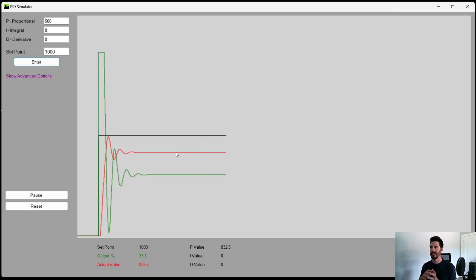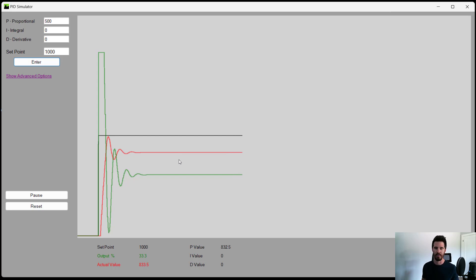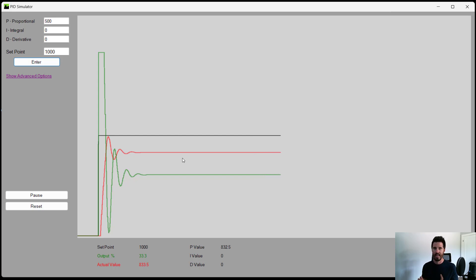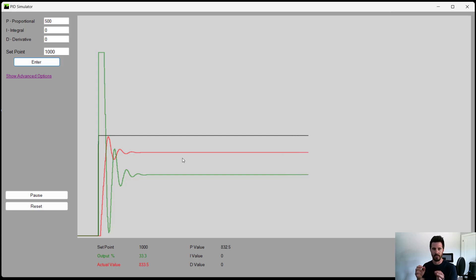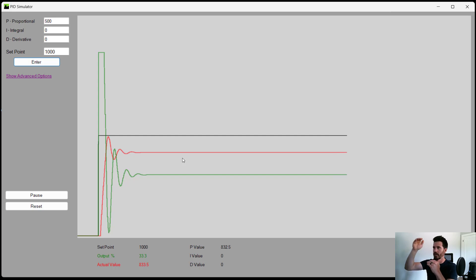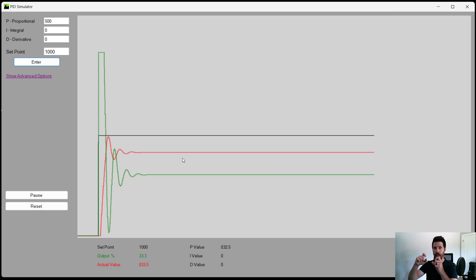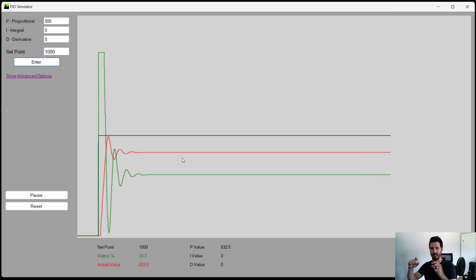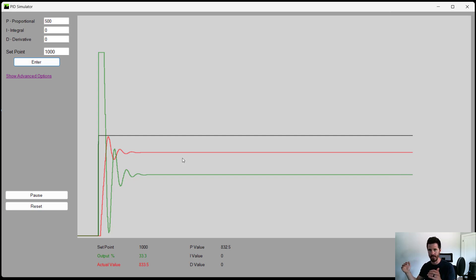Next, we have the integral value, because this is an example of putting a throttle to a position, but never actually reaching the speed. So the integral value, it is a very slow reaction in the beginning, because it's the same thing. It's the integral gain multiplied by your error, or your deviation from what is my actual value, or what is my speed, and what is my set point. The integral multiplies the integral gain by that, multiplied by the amount of time it's been since your actual value has not reached your set point.